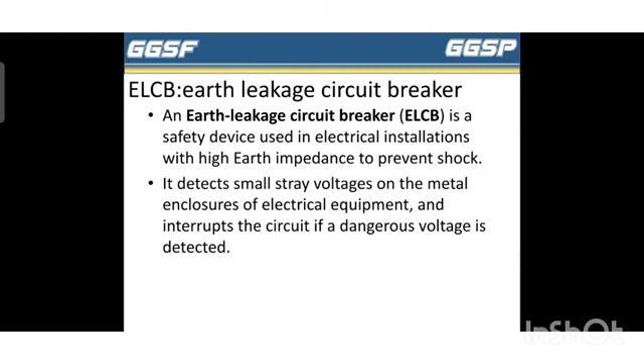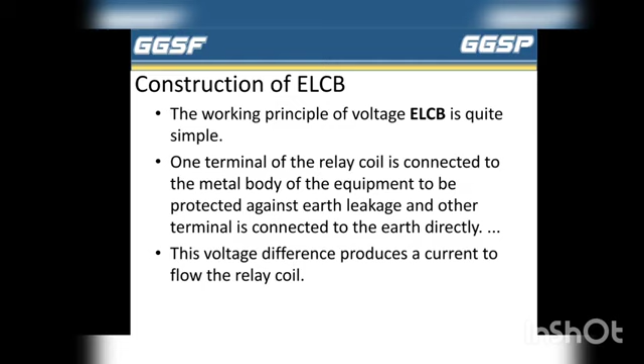Now, first one is construction of ELCB. The working principle of voltage ELCB is quite simple. One terminal of the relay coil is connected to the metal body of the equipment to be protected against earth leakage, and the other terminal is connected to the earth directly. This voltage difference produces a current to flow through the relay coil. Now next one is working of ELCB.